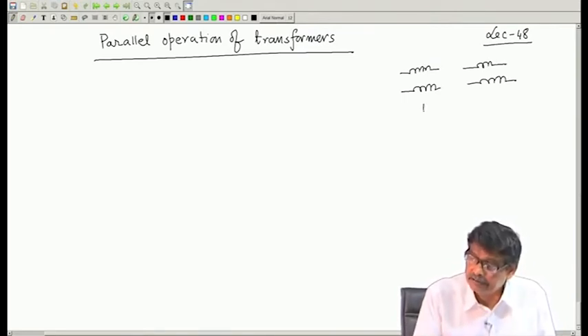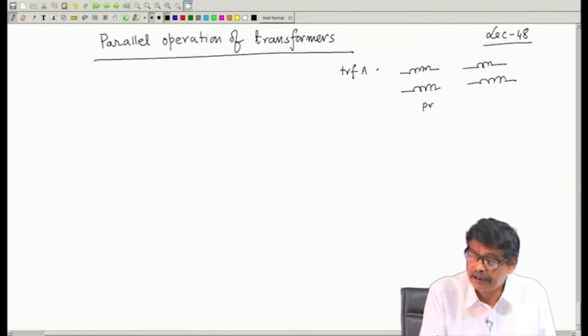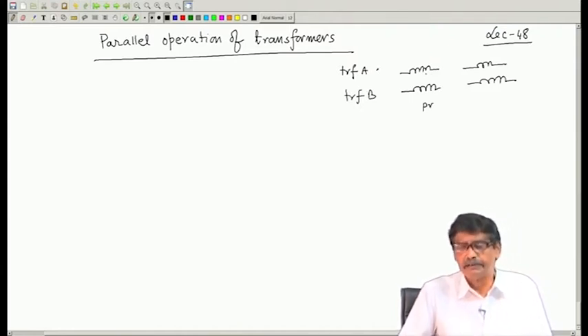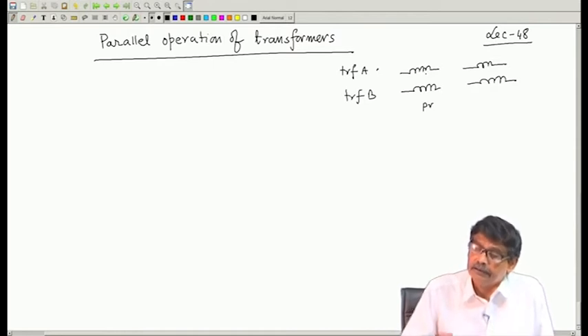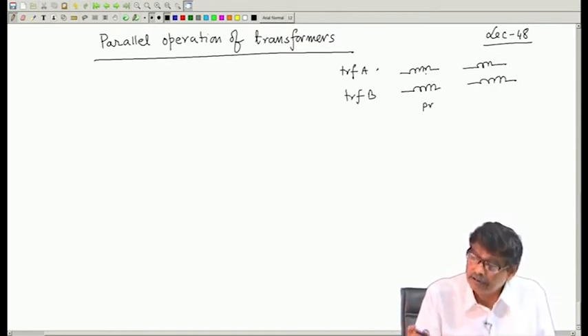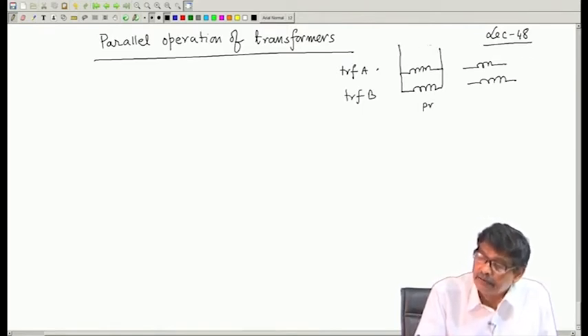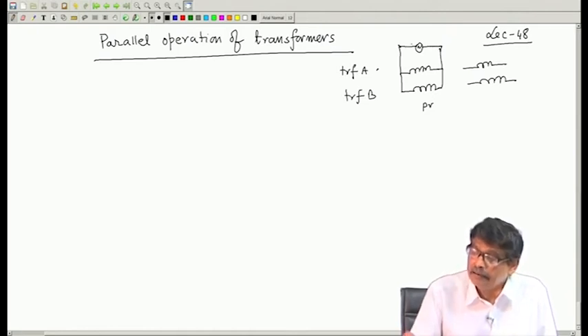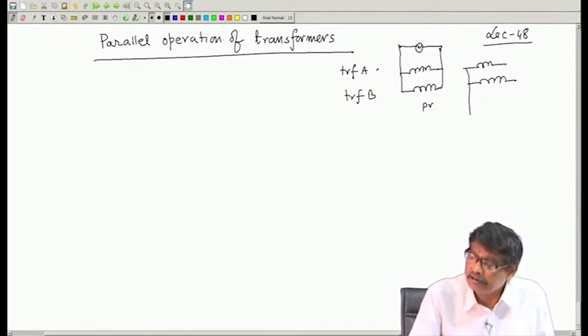These are the primaries of two transformers, say transformer A and transformer B. This is not ABC phase; we will first discuss single phase parallel operation. What does that mean? The primaries will be connected in parallel and excited from a voltage source. The secondary windings will be connected in parallel and the load will be connected.